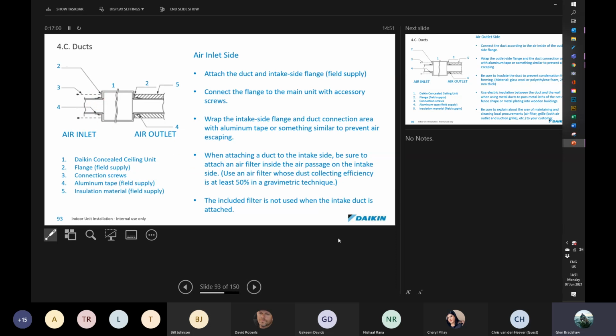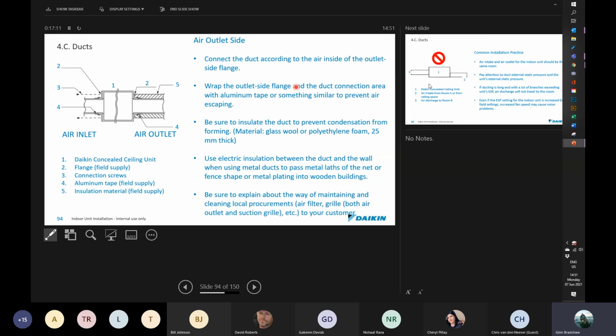Do not put 2 filters in line. And please don't fit the filter and then put ducting over it, because at some stage somebody's got to get in there to get it out and clean it. The outlet side is basically the same thing. Connect the ducting according to the air inside and the outlet side flange, and then wrap the outlet and the duct connection area with aluminium tape. Be sure to insulate the duct to prevent condensation.